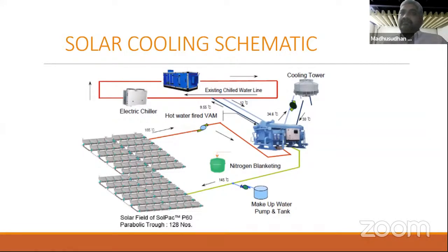Unlike electric chillers, where we can determine what output we want, in solar-based cooling we cannot determine the output we want. We have to take the output we get and modulate the remaining system accordingly. So basically you get whatever free cooling you get here, and the rest you use the electrical chiller for.